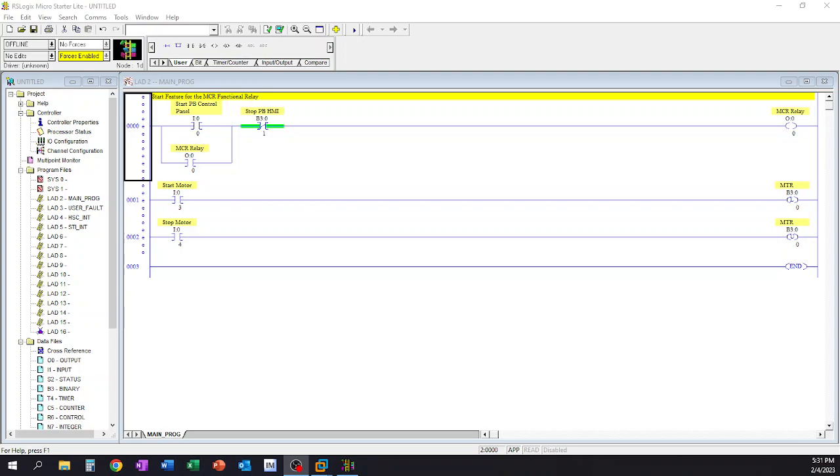RSLogix 500 as well as Studio 5000 RSLogix 5000 offer us the feature of verifying our project, our routine, in two different buttons. One of the benefits of that is the system goes through and verifies that the code is correct. It doesn't say that we programmed it correctly, that it's going to function the way we need it to, but rather it's going to go through its own internal check to make sure that we configured it properly.